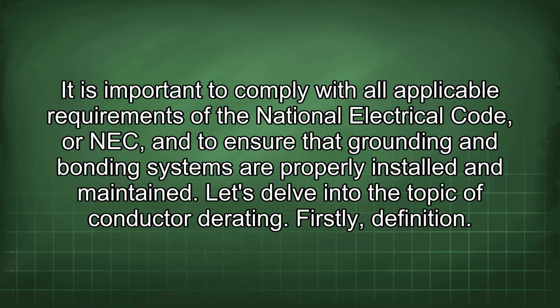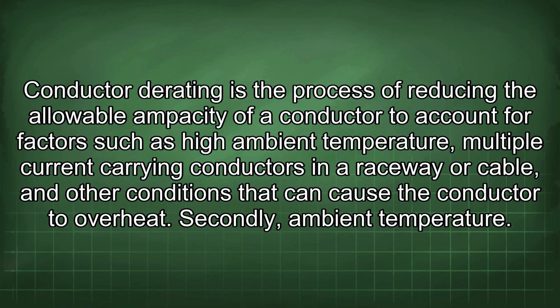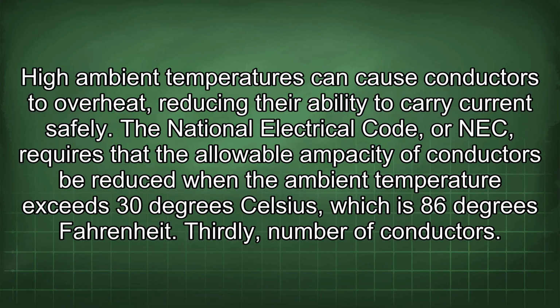Let's delve into the topic of conductor derating. Firstly, definition. Conductor derating is the process of reducing the allowable ampacity of a conductor to account for factors such as high ambient temperature, multiple current carrying conductors in a raceway or a cable, and other conditions that can cause the conductor to overheat. Secondly, ambient temperature. High ambient temperatures can cause conductors to overheat, reducing their ability to carry current safely. The National Electrical Code, or NEC, requires that the allowable ampacity of conductors be reduced when the ambient temperature exceeds 30 degrees Celsius, which is 86 degrees Fahrenheit.